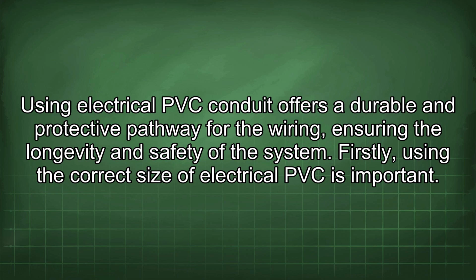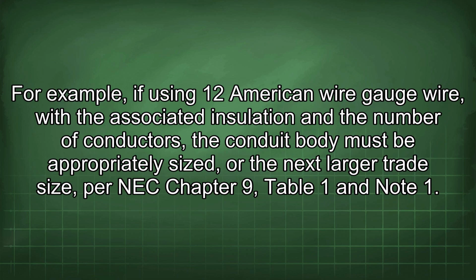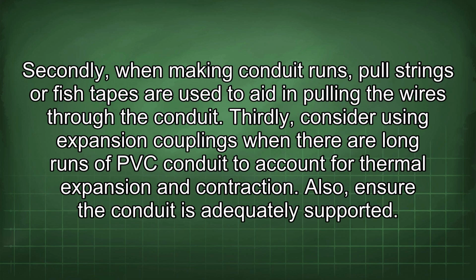Using electrical PVC conduit offers a durable and protective pathway for the wiring, ensuring the longevity and safety of the system. Firstly, using the correct size of electrical PVC is important. For example, if using 12 American wire gauge wire, with the associated insulation and the number of conductors, the conduit body must be appropriately sized, or the next larger trade size per NEC Chapter 9, Table 1 and Note 1. Secondly, when making conduit runs, pull strings or fish tapes are used to aid in pulling the wires through the conduit.